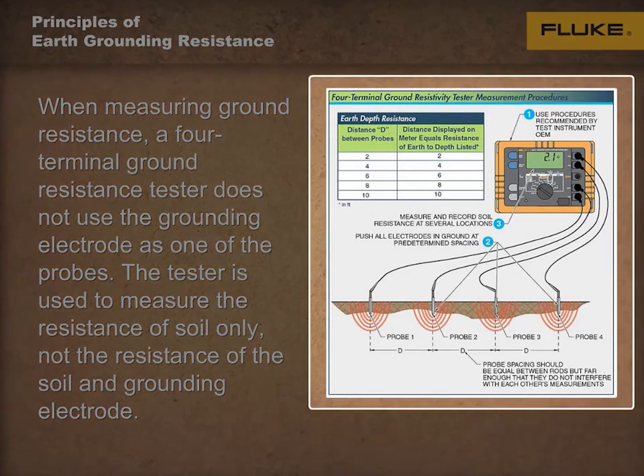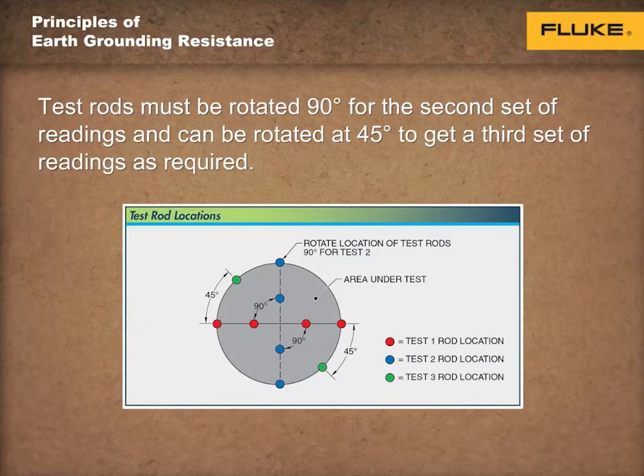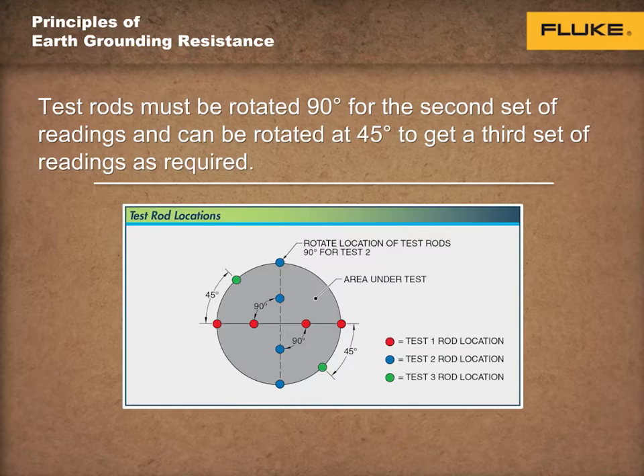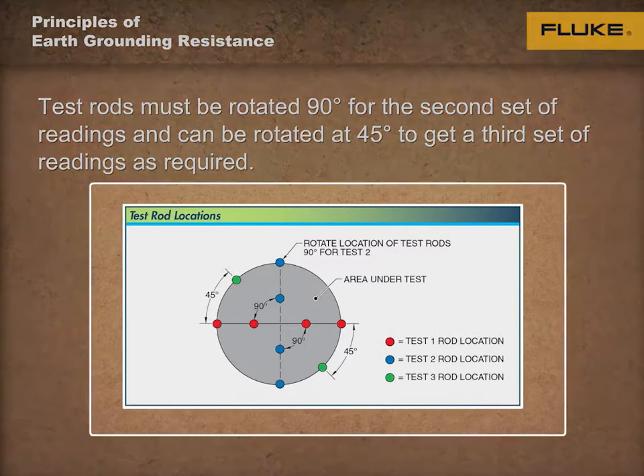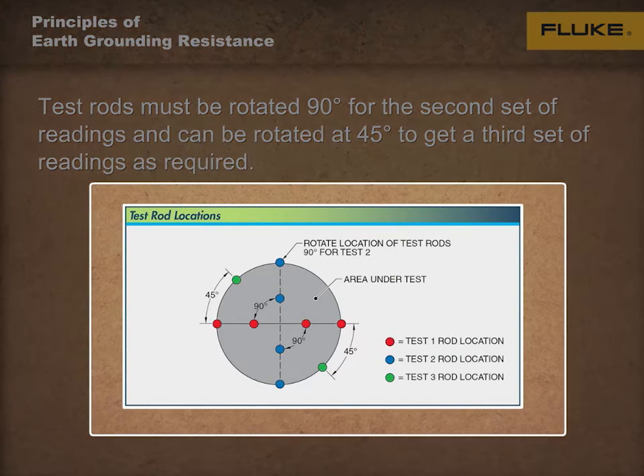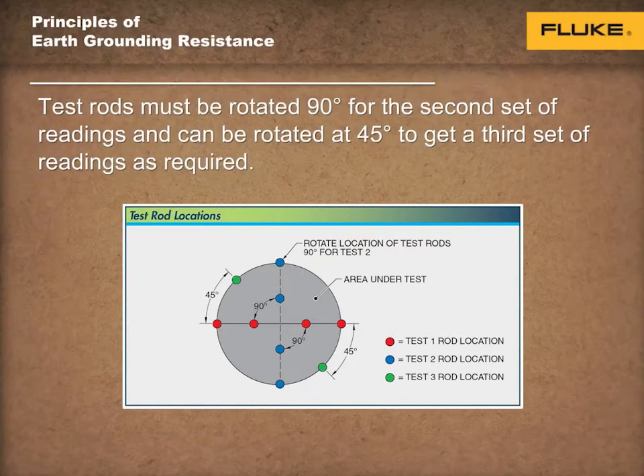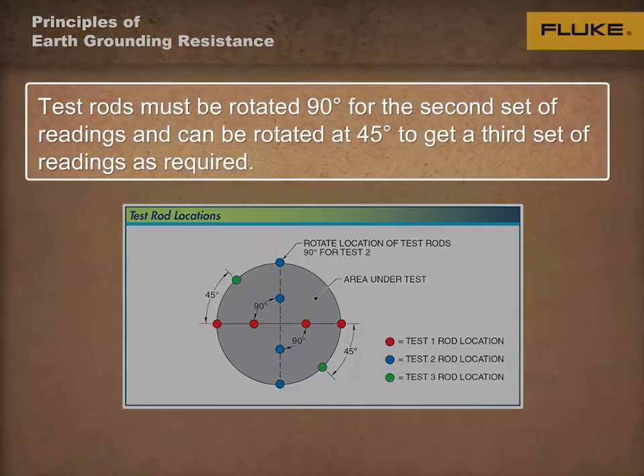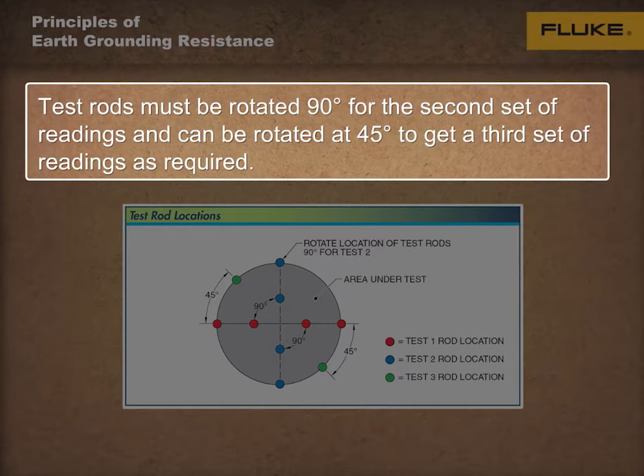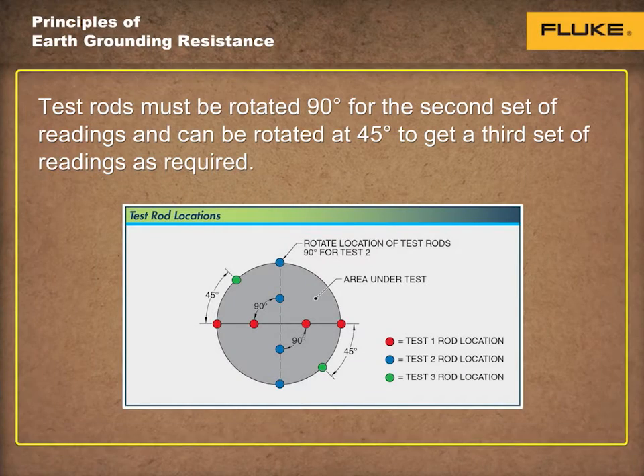This is only if your device does not have memory for storing and retrieving test results. As seen on the screen, test rods can be rotated 90 degrees to get a more accurate indication of the entire soil condition. If the test results vary widely, additional measurements can be taken at 45 degrees to give a clearer picture of the soil conditions.